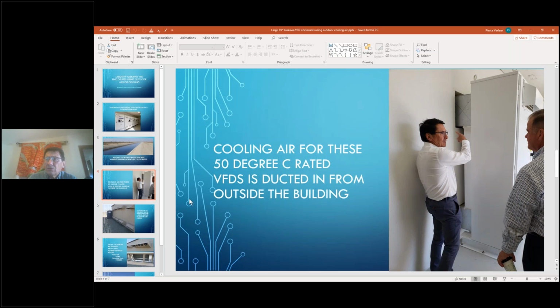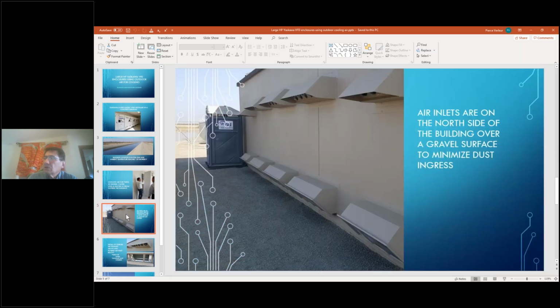plan. The outdoor looks like this. Note we are on the north side of the building. That's logical. We also, in order to reduce a tremendous amount of dust being sucked up into the filters, even with the low air inlet velocity of having the fans at the top, there are the fans, we put gravel out here. None of these things that we've done are significantly expensive. Orienting the building doesn't change the building cost that much, if any. The gravel wasn't that expensive. The doors or the holes for the vents were not that expensive, as long as we gave them the right dimensions before they cast the walls.